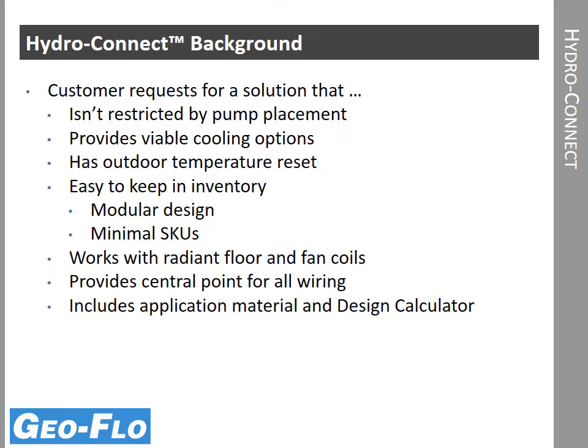One of the challenges with any hydronic system, especially with heat pumps, is finding controls that handle the cooling option properly. Outdoor temperature reset was an important portion of the project, as we have lower water temperatures with milder outdoor air temperatures. Then we have better heat pump COPs, so that really increases system efficiency. And easy to keep in inventory means that modular design and fewer components that can be mixed minimizes SKUs, so inventory is in stock more often for contractors, and it makes it easier for inventory for distributors and manufacturers.